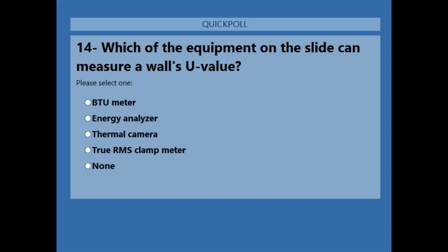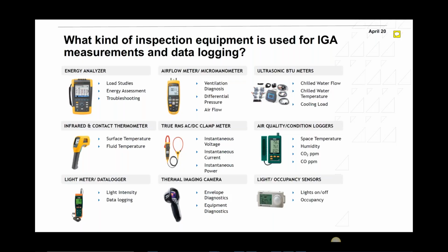Around 72% voted, and the right answer is none. Basically, none of the equipment shown here can give us the U value of a wall. What we would need is a heat flux meter. We need to install that for a long time, maybe 1 week, maybe 2 weeks, to check the heat flux within the wall with the temperatures in and out, and then that would give us the U value of the wall or a roof. Normally we use it for walls or roofs.